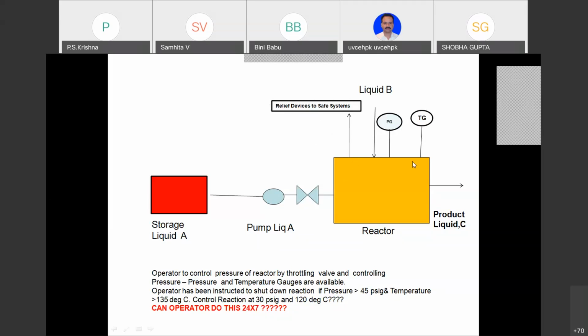steam. Then you are given a pressure indicator and a temperature indicator, and the operator is trained. He says, you tell that operator to control the pressure of the reactor by throttling the valve, and pressure and temperature gauges are available. The operator has been instructed to shut down if the pressure goes above 45 psig and the temperature goes to 135 and above. The normal healthy control reaction is 30 psig and 120 degrees centigrade.